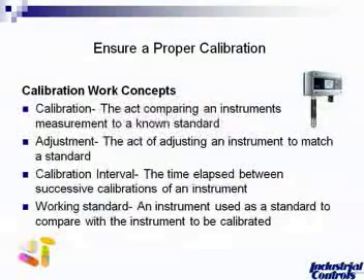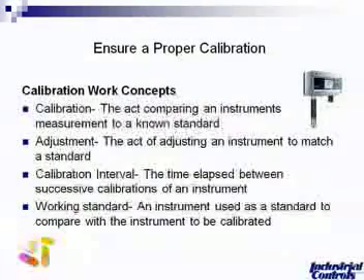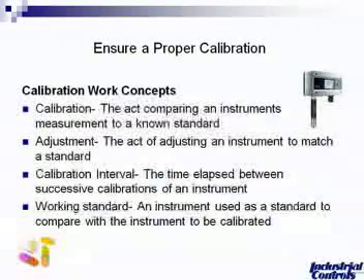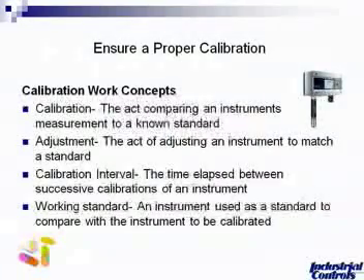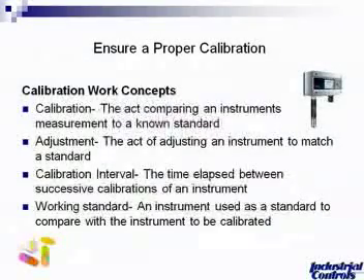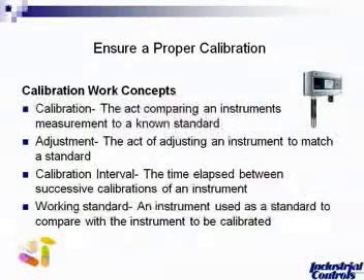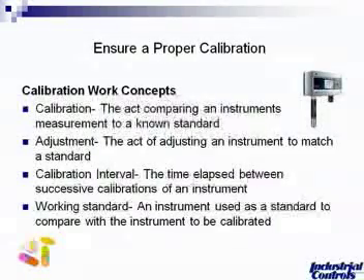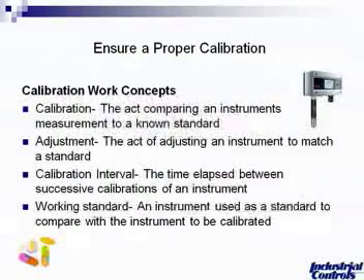How do you ensure proper calibration on these devices? The hardest part about any type of calibration is calibrating against a known reference. How do you know your reference is good? If your reference is no good, then your calibration is going to be no good. You have to be sure that you're calibrating against a known standard. A calibration is an act of adjusting your instrument to match that standard. A working standard is basically an instrument used as a standard to compare with the instrument to be calibrated, such as a handheld.